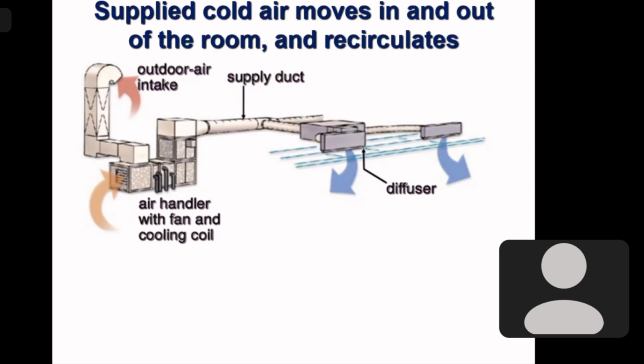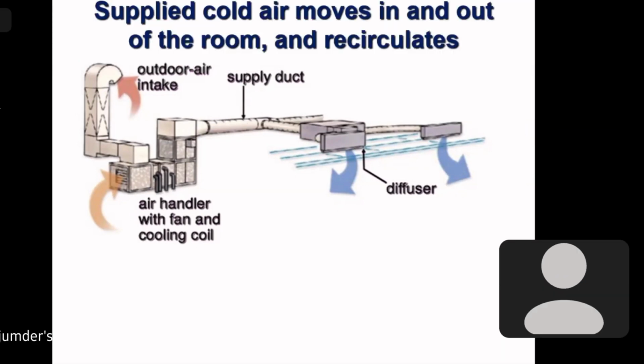So we do it intentionally. Why do we do it? If we allow air to come inside the room from outside in an uncontrolled manner, it will bring the outside dust inside the room. That means the cleanliness of the air-conditioned room will be disturbed. Instead, we make the room pressure a little above the outside atmospheric pressure, so that air never comes in, air always goes out. There is no infiltration of air. There is exfiltration of air all the time. So the room remains cleaner. So this is how the air circuit is.